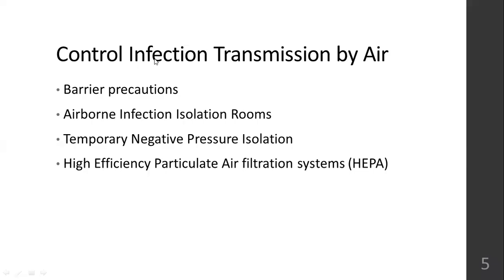A temporary negative pressure isolation room can be created if you don't already have an airborne infection isolation room. HEPA filtration has to be done - the HEPA filtration system has to be put in positive pressure isolation rooms so that you can protect immunocompromised people from getting any infection.